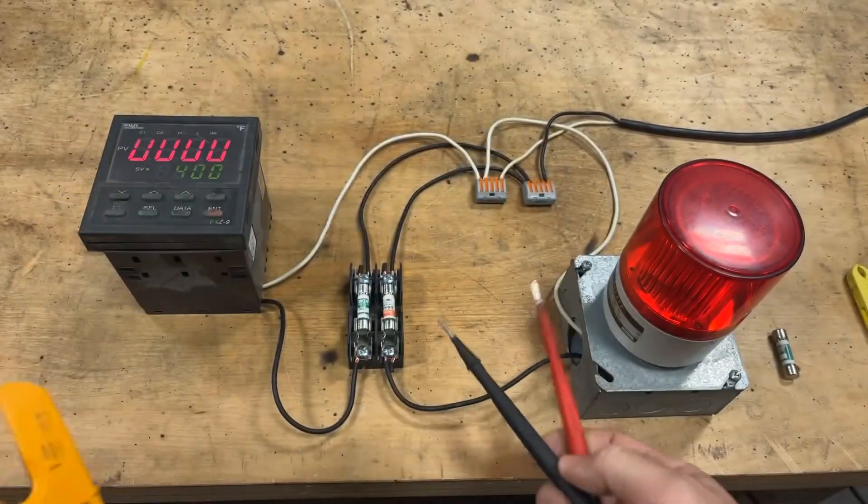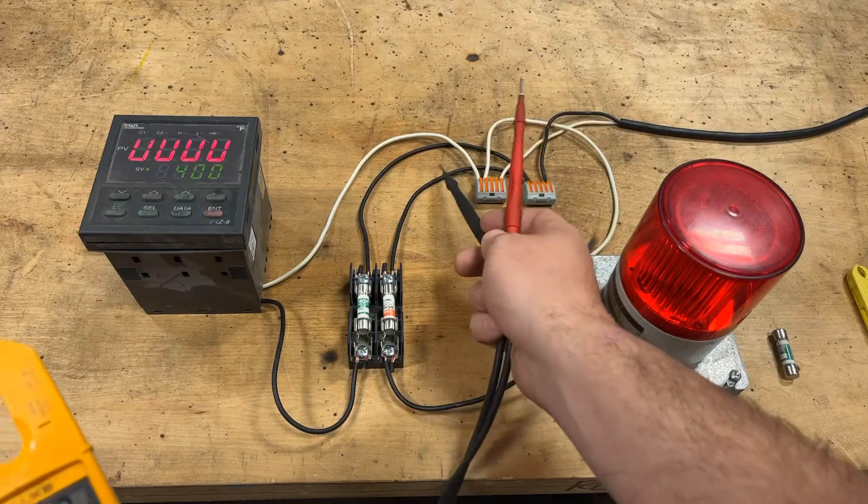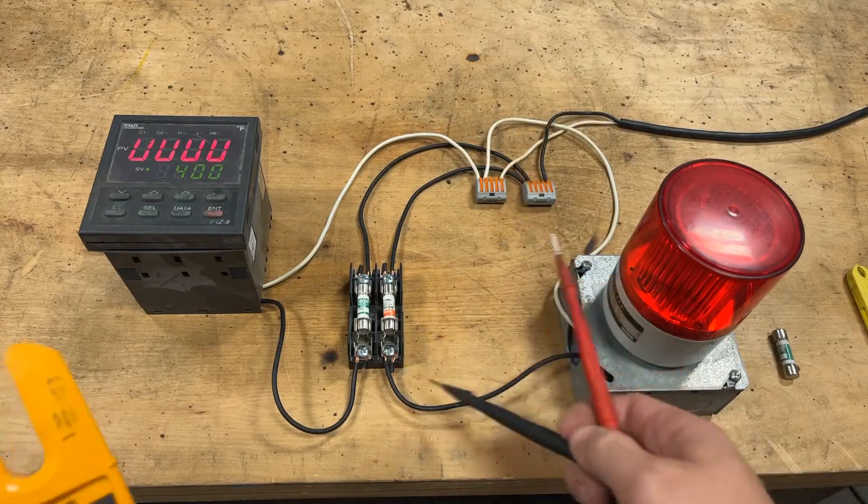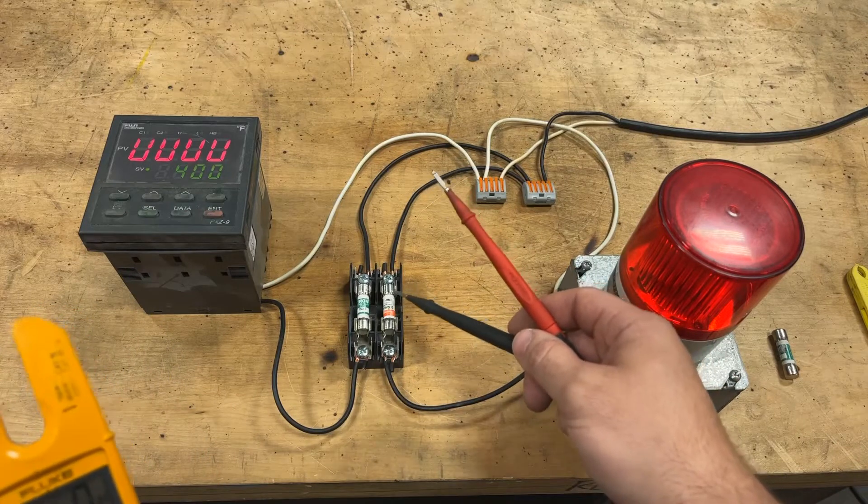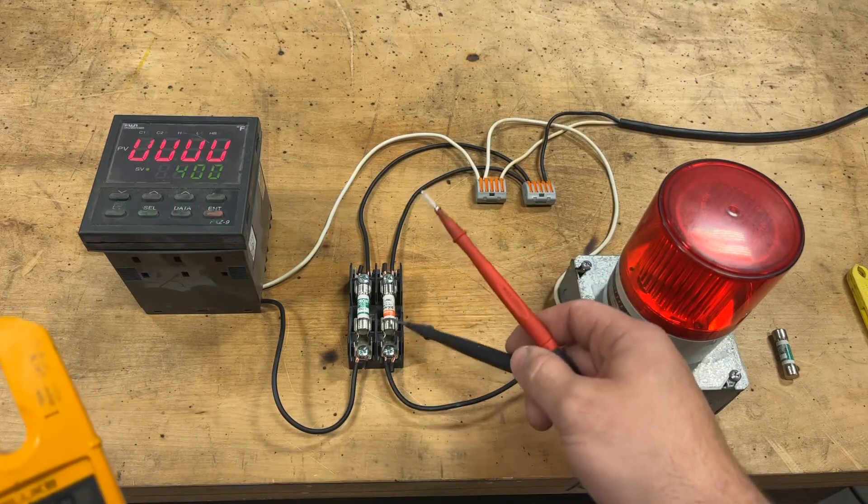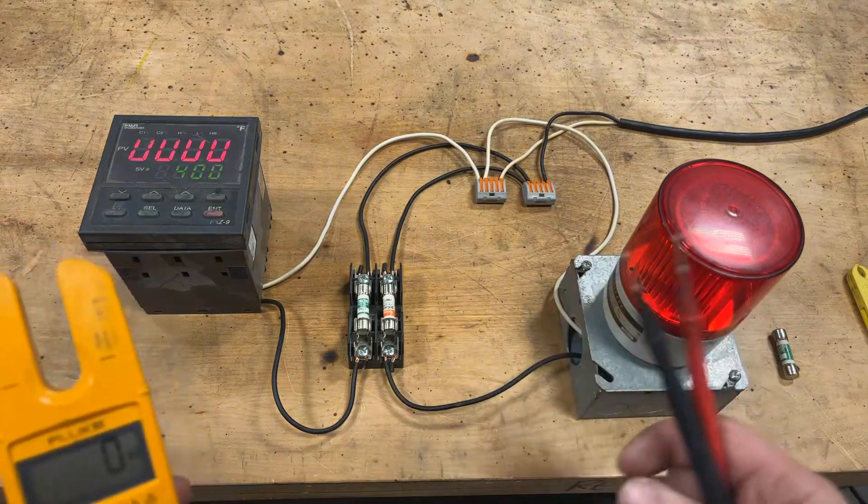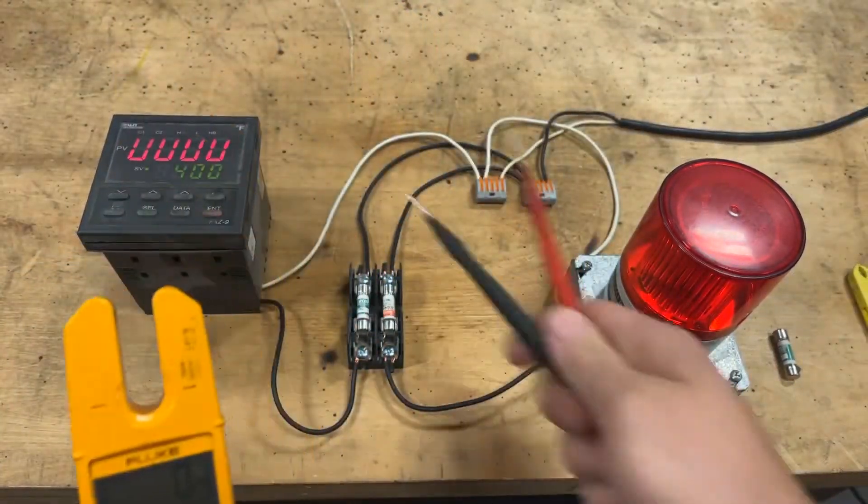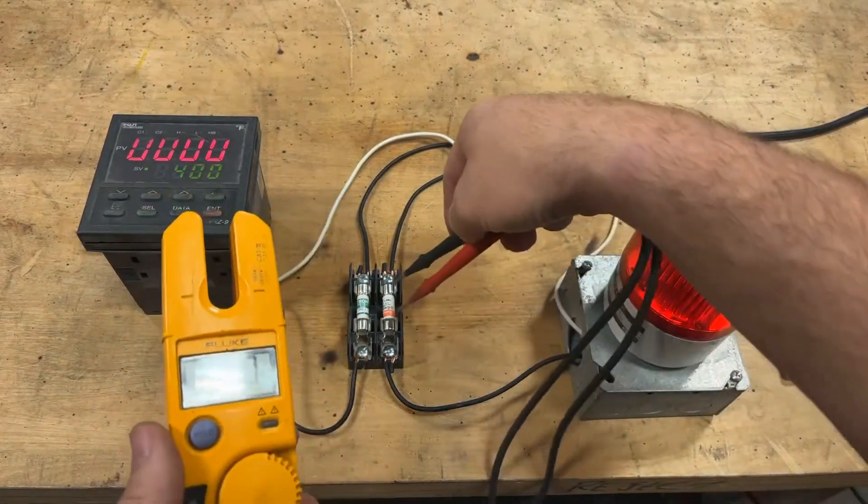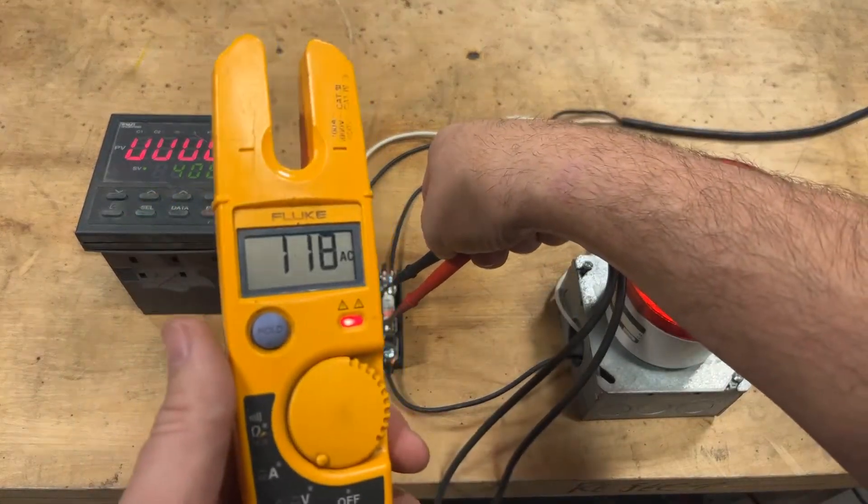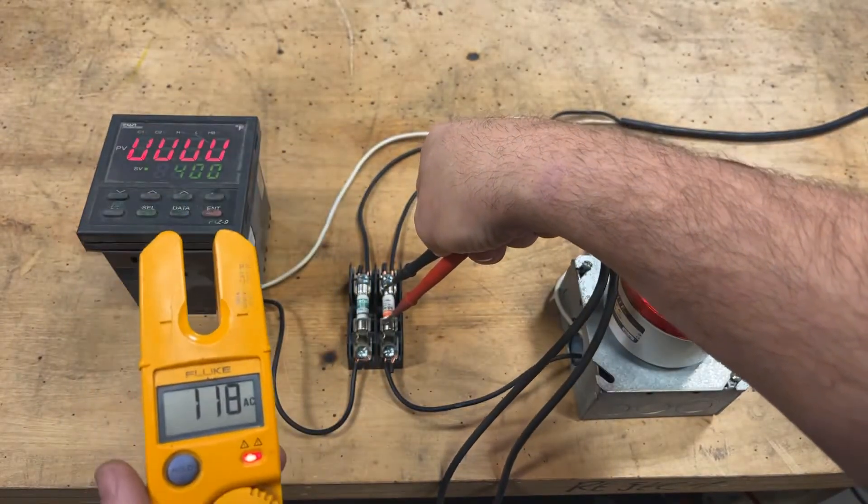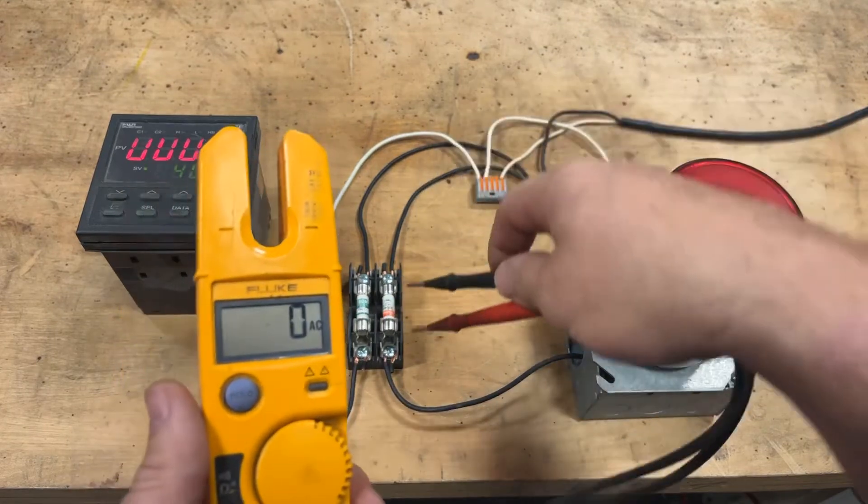So if you think about a fuse in a live circuit, I have power coming in and power going out to the load. If this fuse is blown, that means I have power on the top side of this fuse and none on the bottom side. Guess what? That's a differential we can measure with voltage while this circuit is live. So let's go ahead and check this fuse with voltage. Look at that. I have a difference in voltage on this fuse. That means this guy is dead.